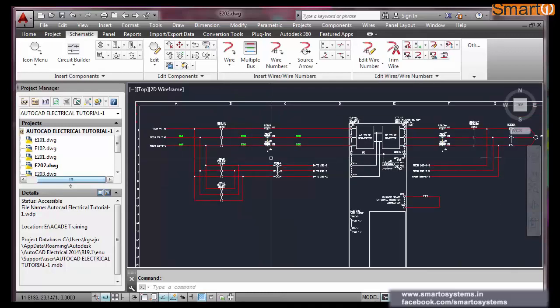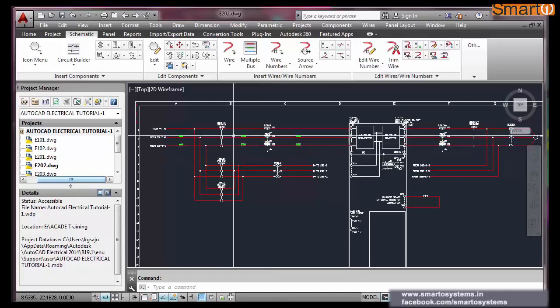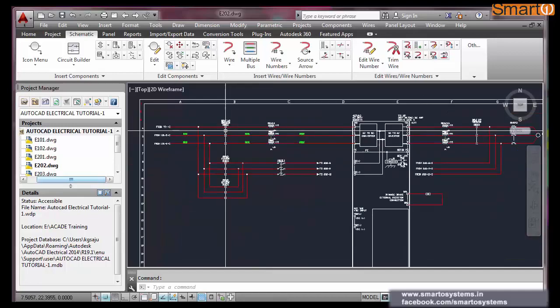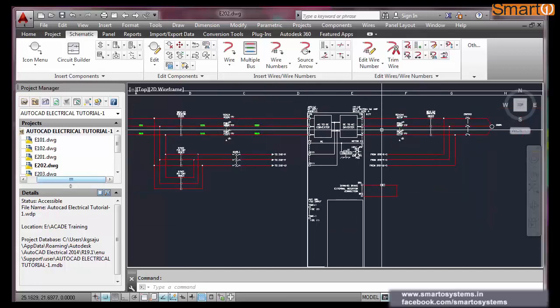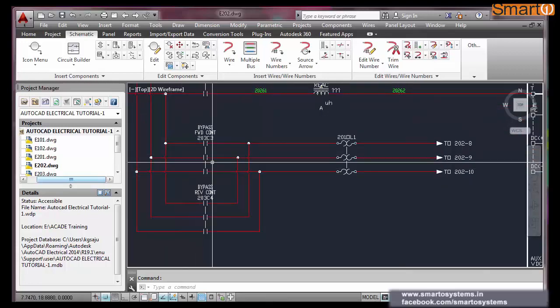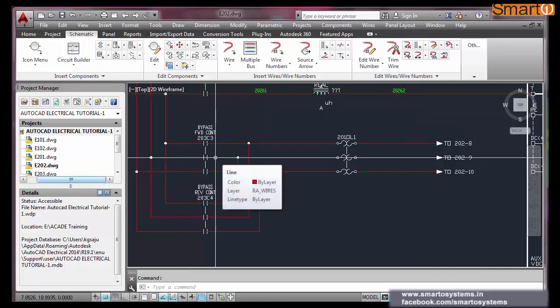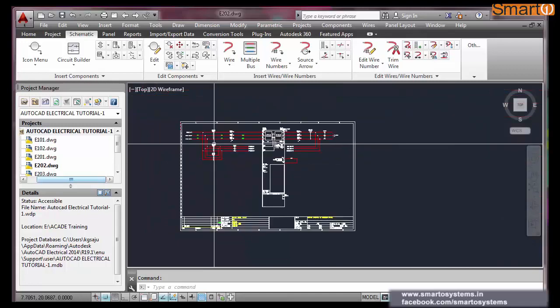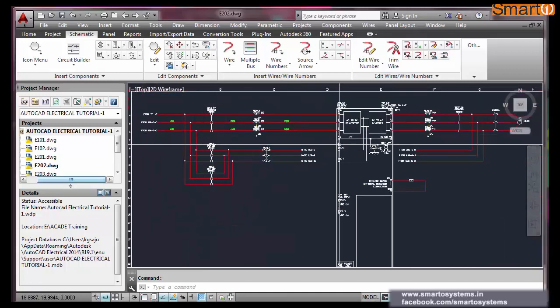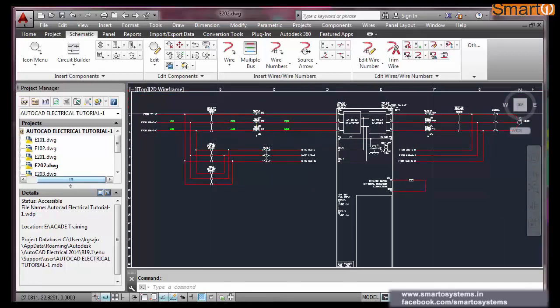You should always remember, while contactor 1 and contactor 2 are on, that means when the drive is on, this should be off. So we need some interlocking between these two sets. When the bypass runs, the drive won't run.